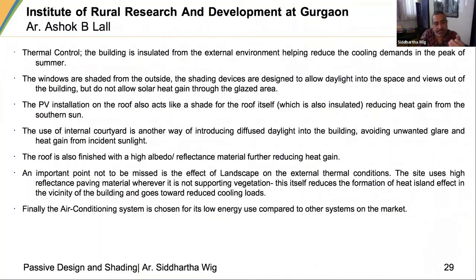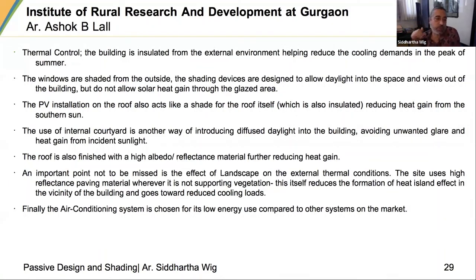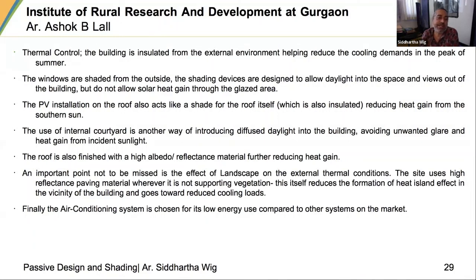The buildings were insulated from the external environment, reducing cooling load. Windows were planned with external shading. PV installation on the roof also helped to insulate the roof. An internal courtyard had louvers on top that aided in providing a cooler area from which cool air came into the building. The roof had a high-SRI reflective paint, reducing heat gain. Landscape was a very important part — native species were selected with consideration of shadow formation, transpiration rates and the cooling potential of that transpiration.